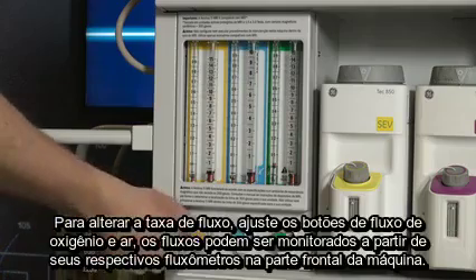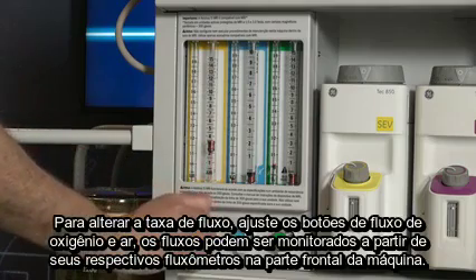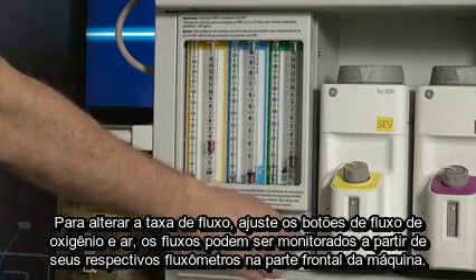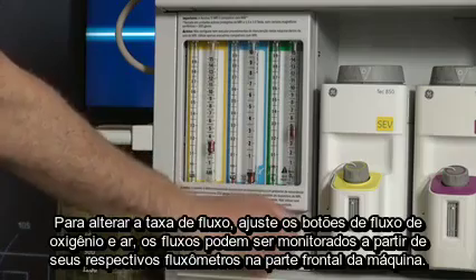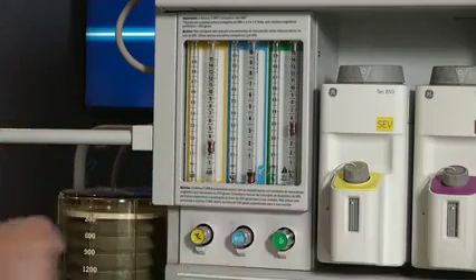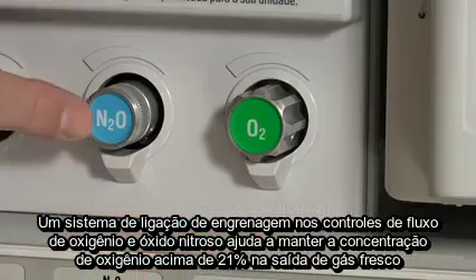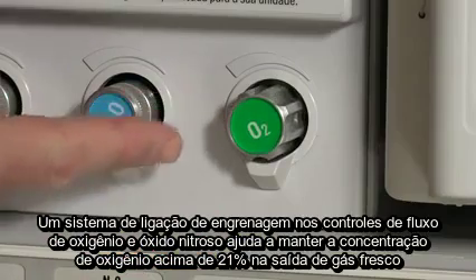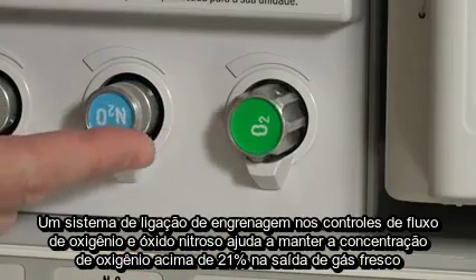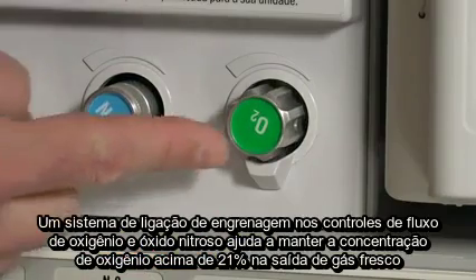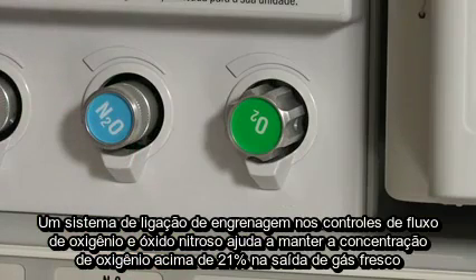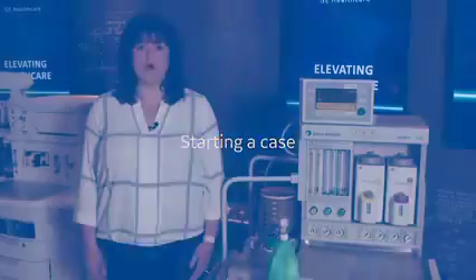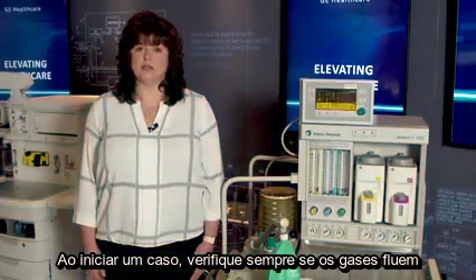To change the flow rate, adjust the air and oxygen flow knobs. The flows can be monitored from their respective flow tubes on the front of the machine. A gear linkage system on the nitrous oxide and oxygen flow controls helps to keep the oxygen concentration higher than approximately 21% at the fresh gas outlet. When starting a case, always ensure gases are flowing.